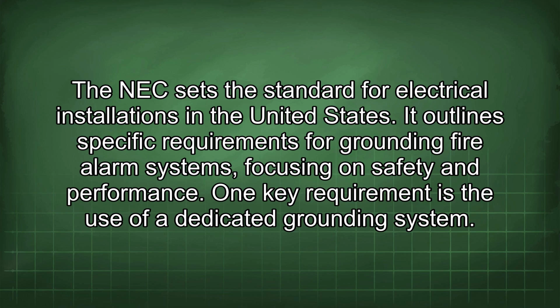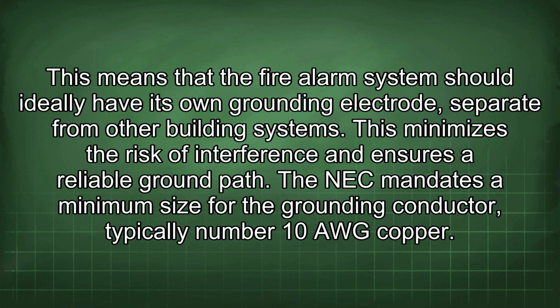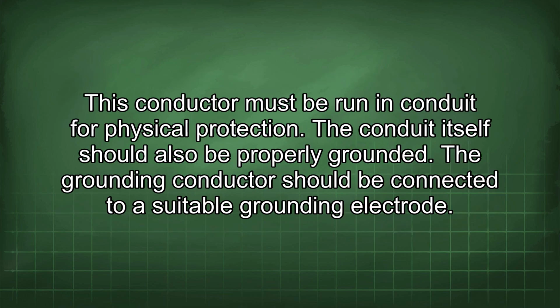One key requirement is the use of a dedicated grounding system. This means that the fire alarm system should ideally have its own grounding electrode, separate from other building systems. This minimizes the risk of interference and ensures a reliable ground path. The NEC mandates a minimum size for the grounding conductor, typically number 10 AWG copper. This conductor must be run in conduit for physical protection. The conduit itself should also be properly grounded.